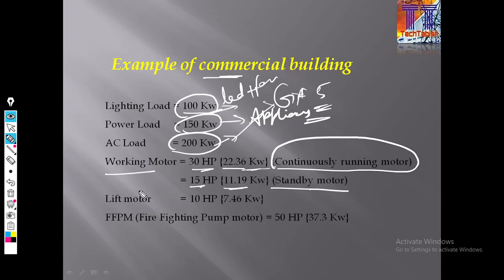So we have taken the working motor which is continuously running and the standby motor. After that we are taking the lift motor, that is 10 HP, 7.46 kilowatt. The last is firefighting pump motor which is 50 HP and the power is 37.3 kilowatt. So these all are the connected load which are connected in this commercial building.